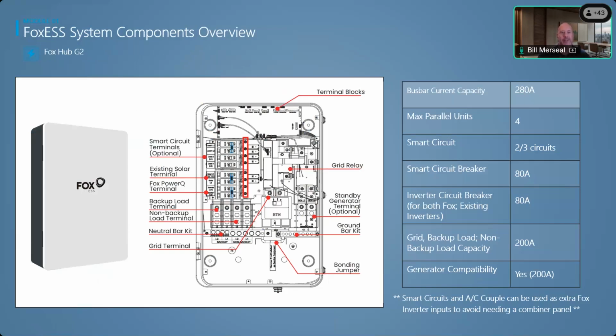What's nice is the program works so that once it hits a certain state of charge, which you can manipulate, say 90%, the generator turns off. Then it uses battery power until it reaches your minimum state of charge, say 20%, at which point the generator turns back on, powers the home loads, and any excess charges the battery.